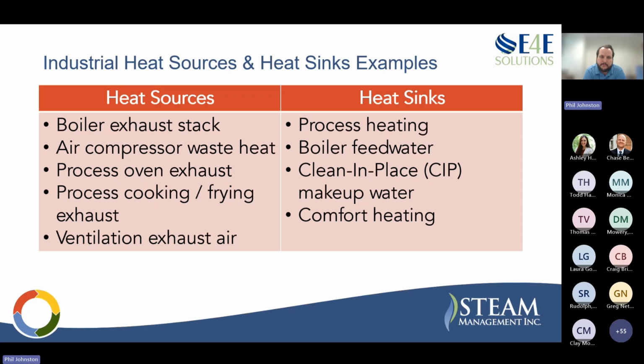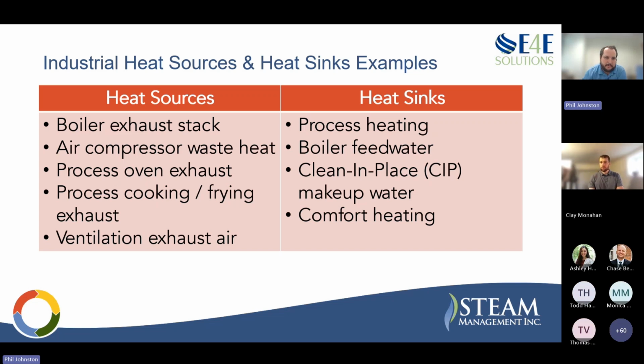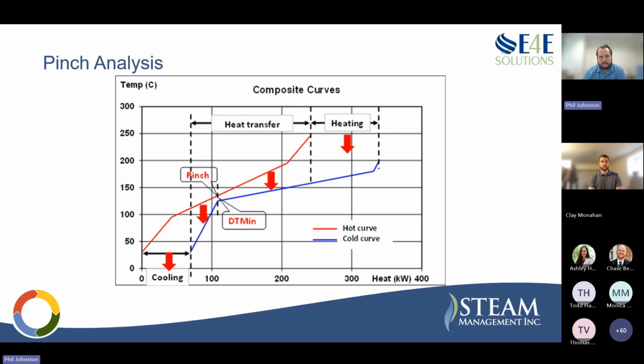So yeah, all this is really driven by temperature, and that leads into my next slide, which is the pinch analysis. If you're not familiar with this, you've got the red line there, which is the hot curve, so that's your heat sources, and your blue line is the cold curve, or your heat sinks. What we're trying to look at here is whether there is enough heat available at the temperatures we need it to serve all the sinks that we have. Pinch analysis allows you to do that. Where those curves approach and almost touch each other is the pinch of the whole analysis, and it really drives how much you can do.